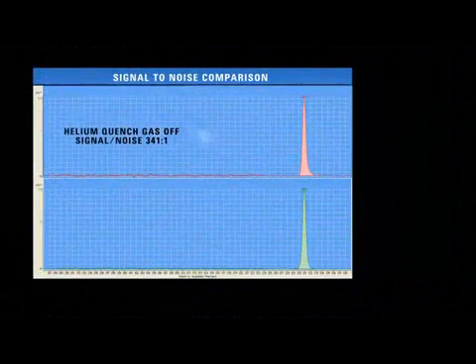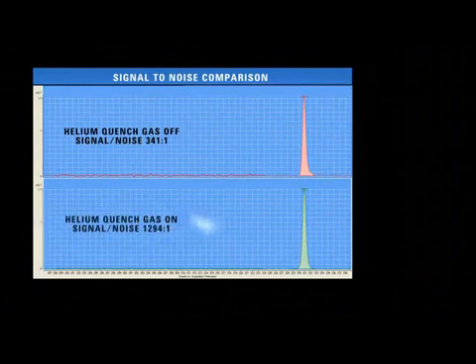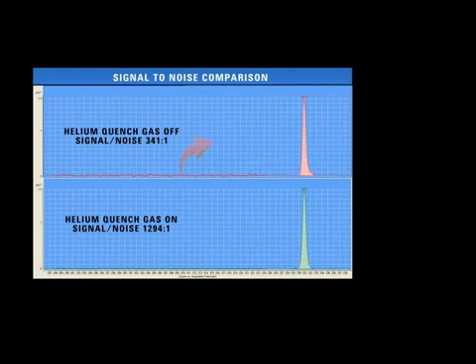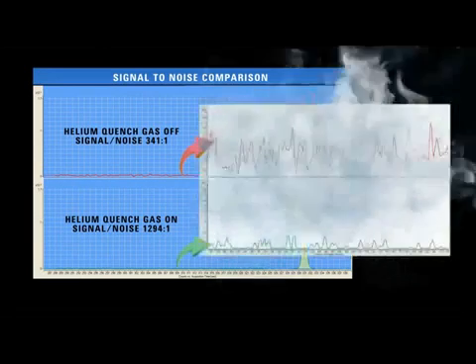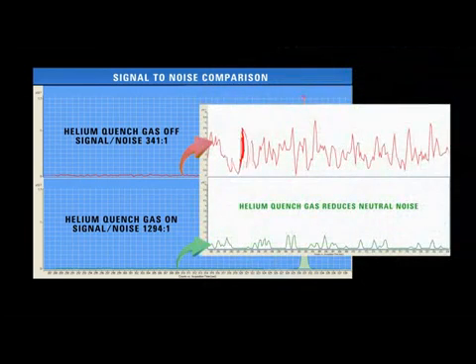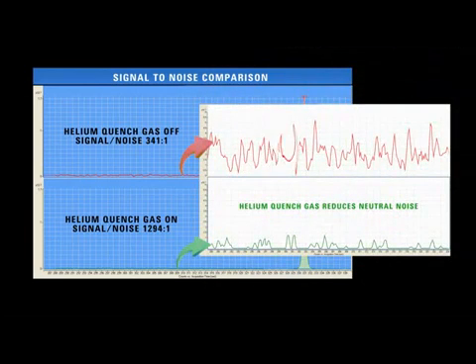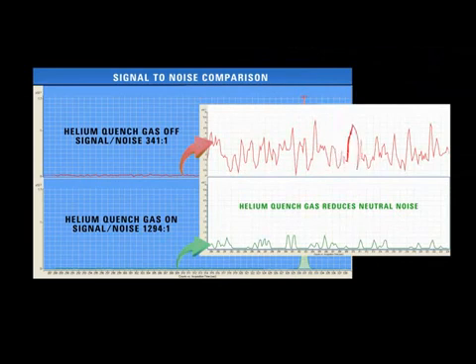A comparison of signal-to-noise ratio with and without helium quenching shows the benefit of this technology. Helium quenching has no effect on product ion signal, but the neutral noise component is reduced by a factor of four. This technical breakthrough means lower limits of detection and quantitation.